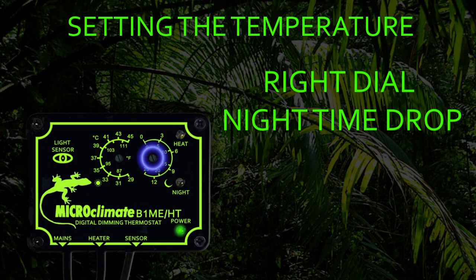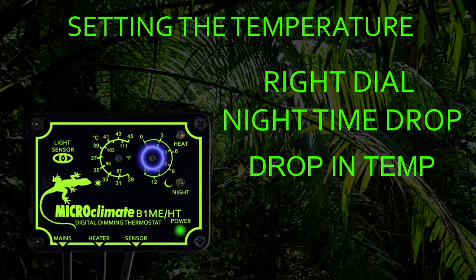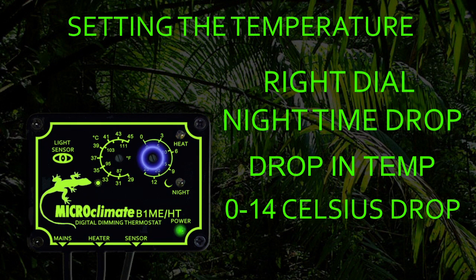The right temperature control dial with the symbol of the moon is used to set the nighttime temperature drop. Please note this is a drop in temperature. So for example, if your daytime temperature is set to 30 degrees and you require the nighttime temperature to be 25 degrees, set the right hand dial to a 5-degree drop. Or if you require the temperature to drop to 20 degrees, then the right hand dial should be set to a 10-degree drop. The temperature can be dropped between 0 and 14 degrees from the daytime temperature.